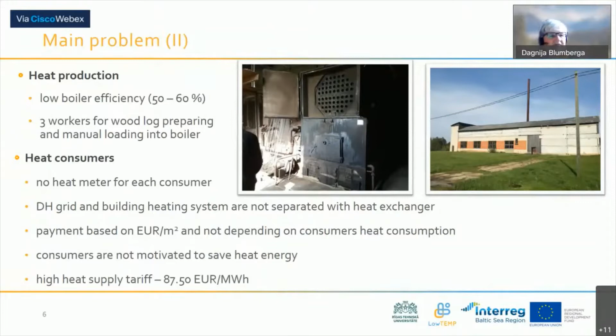The aim of this pilot project was to determine what changes were needed in Beļāva district heating, and what direction those changes should take. When we started, Gulbene municipality knew they would install a new boiler in the old boiler house. We discussed participation in this project, and they understood this could be a good case and a challenge, potentially to continue in other boiler houses in Gulbene municipality. The main idea was to reduce the heat tariff and achieve a low temperature district heating system as a pilot case.